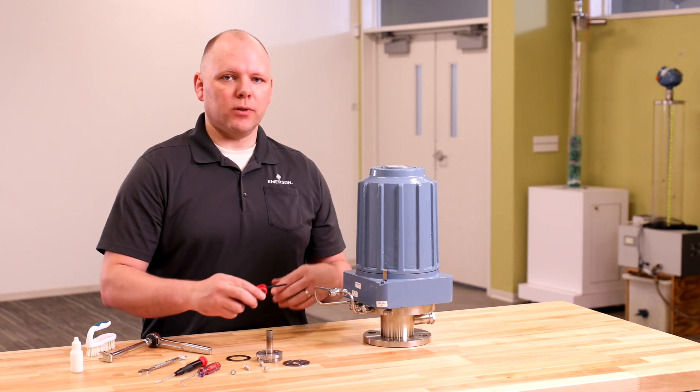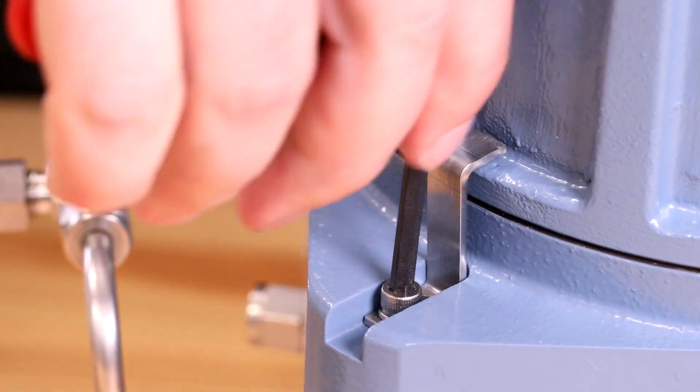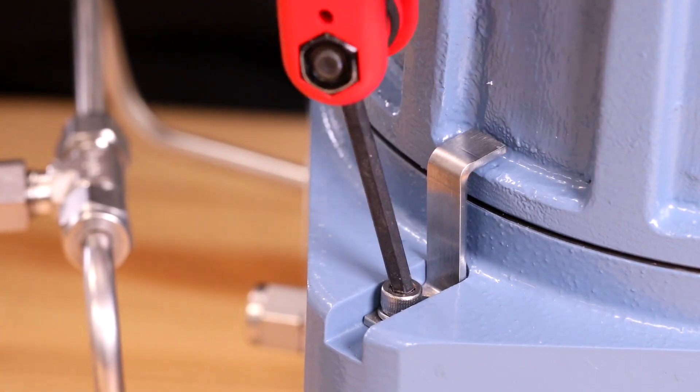To help ensure safety during replacement, make sure the power is disconnected and all components have cooled to room temperature. To begin, loosen the screw on the locking clip with a 4mm Allen wrench and slide the locking clip away from the cover, then re-tighten the screw.